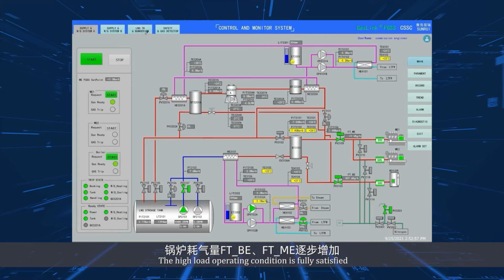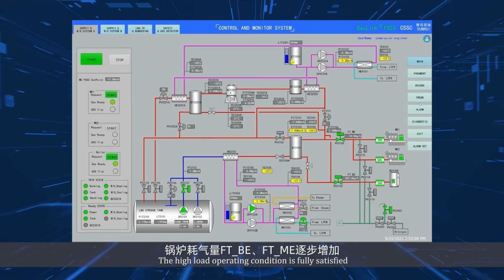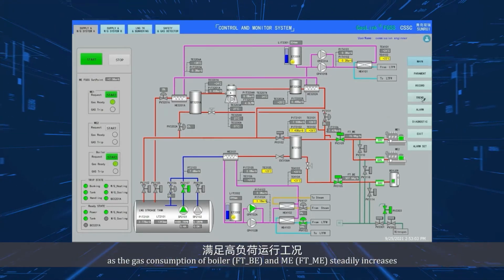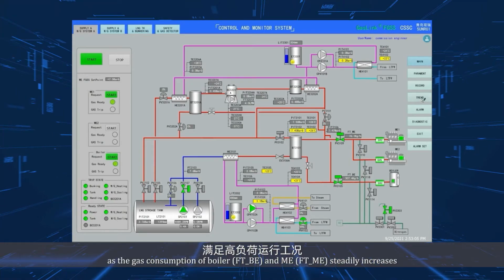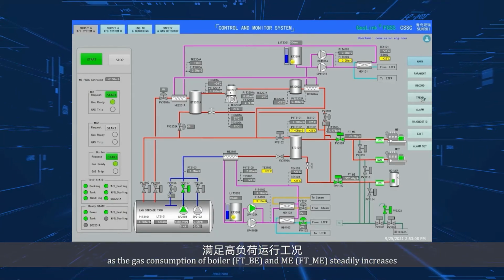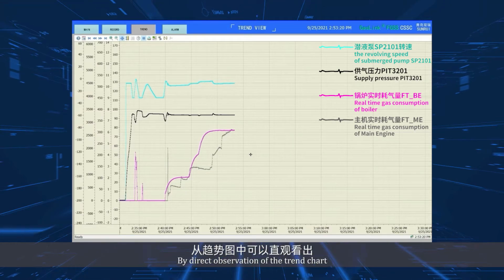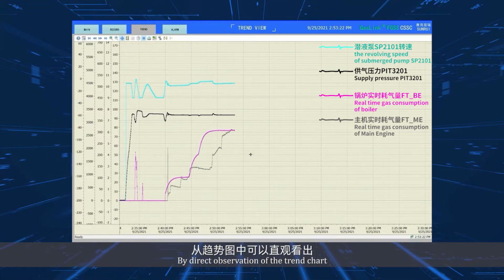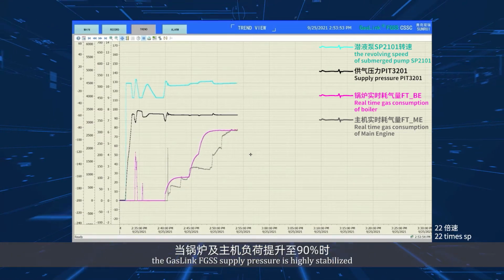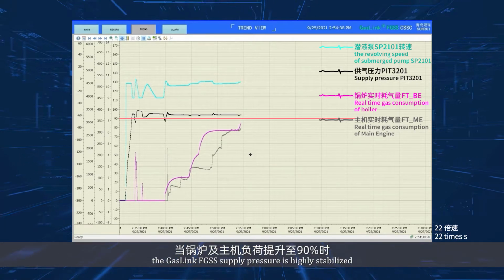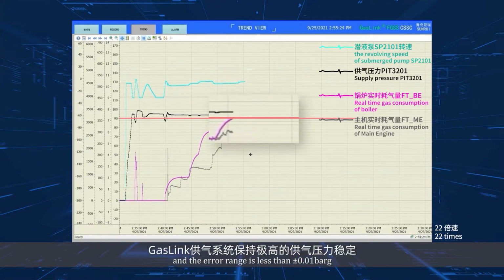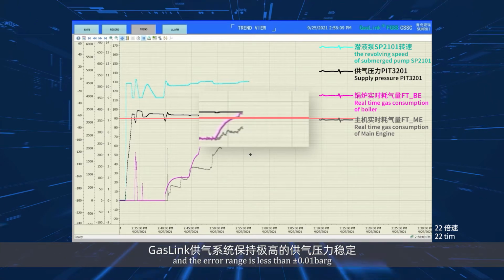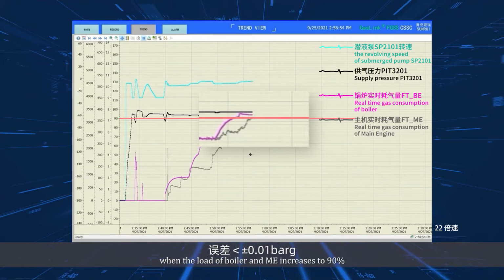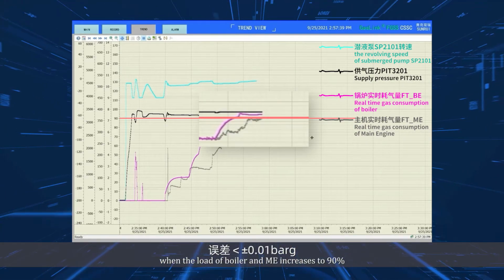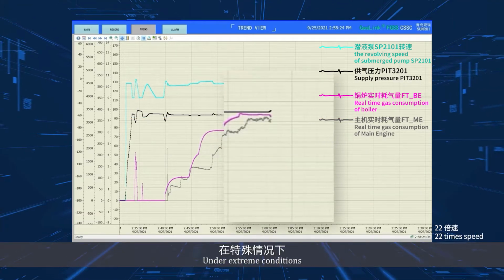The high load operating condition is fully satisfied as the gas consumption of boiler, FT_BE and ME, FT_ME steadily increases. By direct observation of the trend chart, the Gaslink FGSS supply pressure is highly stabilized, and the error range is less than ±0.01 bar when the load of boiler and ME increases to 90%.